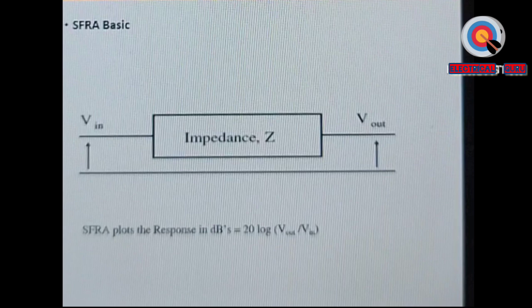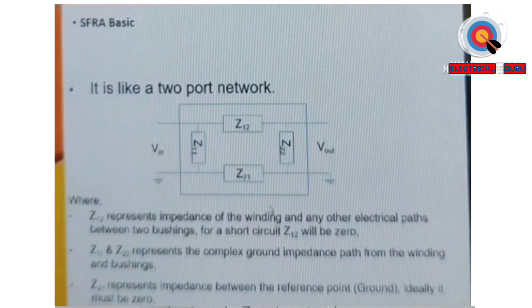So it's like a two-port network. So we have a primary, that is Z11, and a secondary, which is Z22. Between primary and secondary we have Z12, and between primary and earth, or the windings and earth, that is Z21. So these impedances are calculated, checked, and then we see how it behaves.